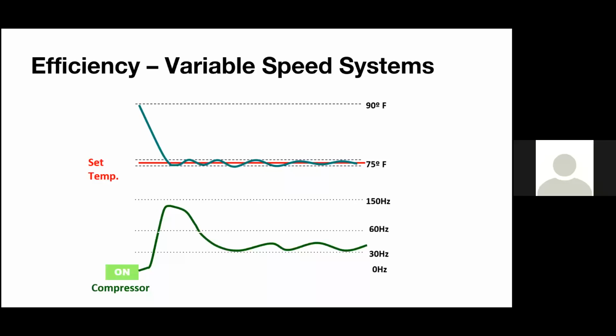It's not efficient. Whereas you size a variable speed compressor or a heat pump system for peak load, on a mild day, a spring day, if it is 70 degrees, it's going to ramp way down low to get exactly the right set point and use exactly the amount of energy it needs in order to cool off that space. And this is where the part load efficiency happens. And this is where we're going to start talking about the different types of efficiency and how they're comparable.